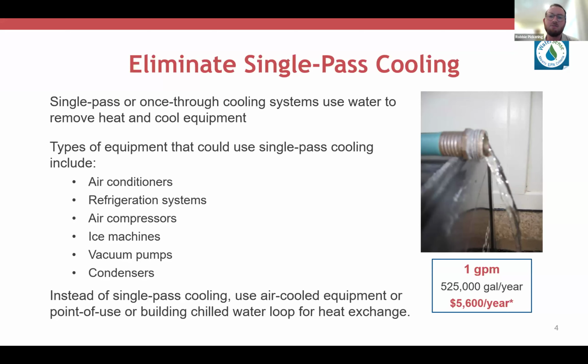In laboratories, you might find this associated with air conditioning units or HVAC equipment, walk-in freezers or refrigerators, ice machines, vacuum pumps, condensers, air compressors, things like that. The hose pictured on the slide is flowing at about 1 gallon per minute, and that's a typical flow rate you might see for single pass cooling systems. At this rate, you're going to be using over 500,000 gallons a year, which will cost you more than $5,600 in water and sewer bills.